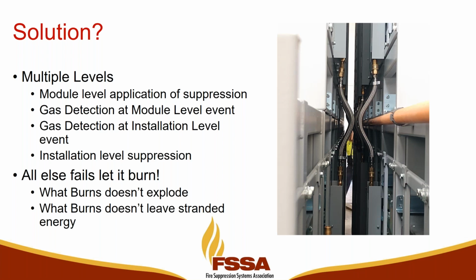I made a comment earlier that what burns doesn't leave stranded energy, but keep in mind that's complete combustion. If you don't have complete combustion, then yes, you have the potential for damaged batteries. UL will not run fire tests on batteries on Thursday or Friday, because they've got to sit around for two or three days to make sure they don't reignite. That's a very real possibility.